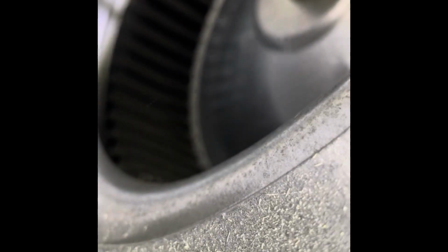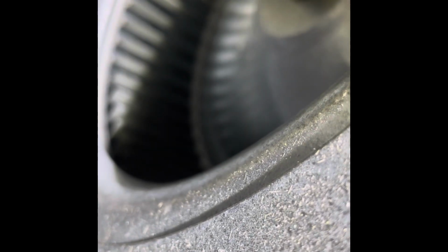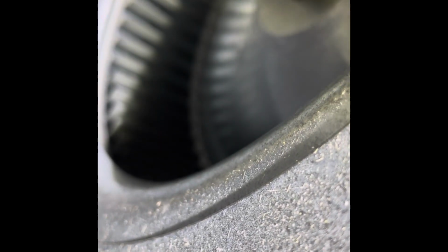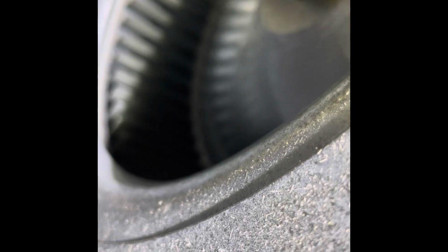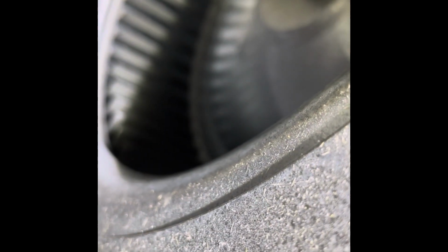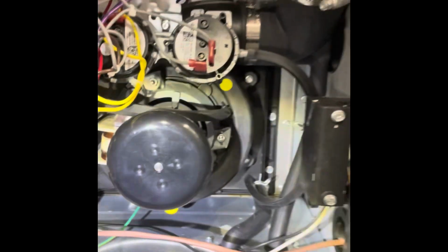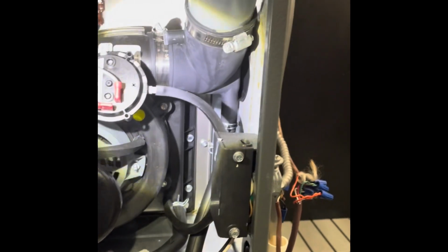Now, if we go over to this side here, I don't know if I can get a good shot of it, but this in here is the blower wheel. Those blower wheels are notorious for picking up pet hair. If a house is being smoked in, it gets a lot of debris on those fins, in turn taking our airflow away. So on a maintenance, they should be peeking in here, making sure your blower wheel's good. This one is good. Now I'm gonna clear out all the condensation lines.